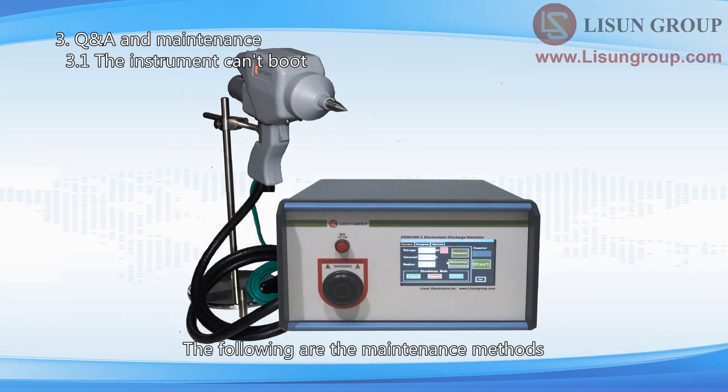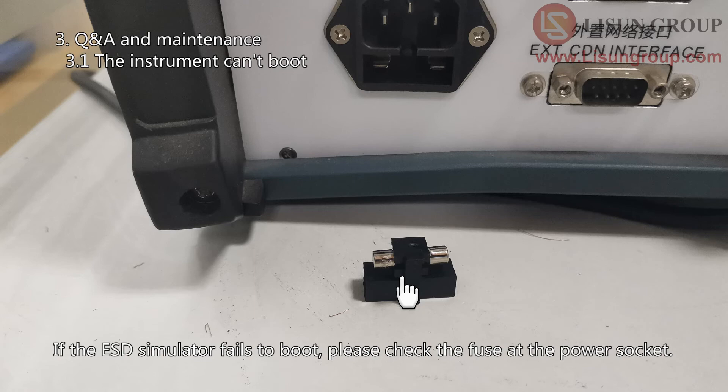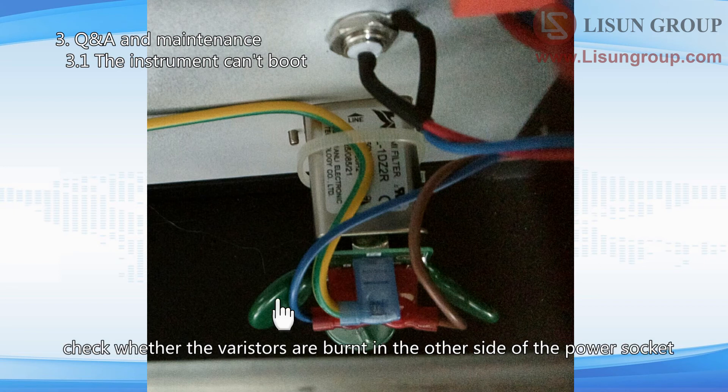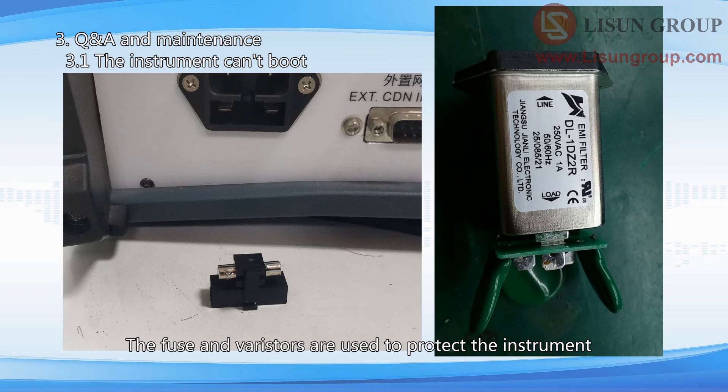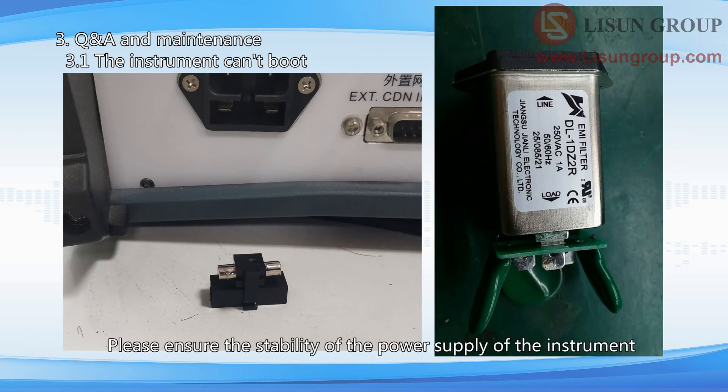The following are the maintenance methods. If the ESD simulator fails to boot, please check the fuse at the power socket. If the fuse is not damaged, please open the equipment carefully and check whether the varistors are burnt on the other side of the power socket. The fuse and varistors are used to protect the instrument — if there is a problem with the power supply, the fuse or the varistors may be burned. Please ensure the stability of the power supply of the instrument. If necessary, you can buy Lisun's regulated AC power supply.